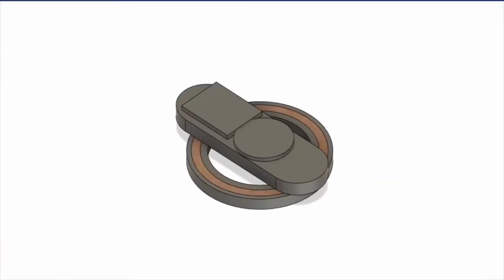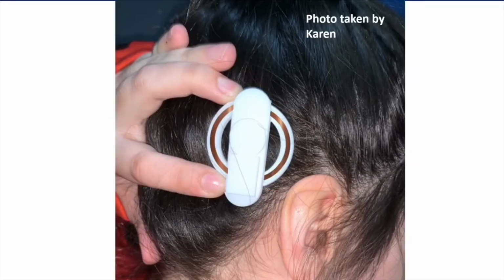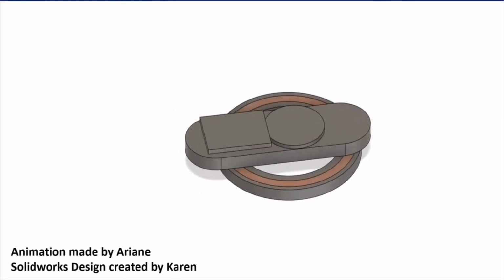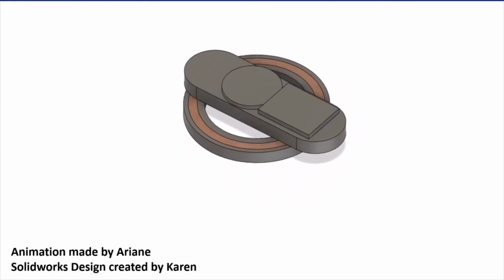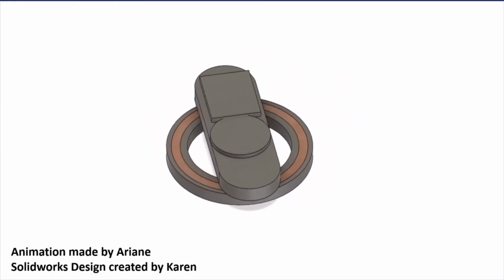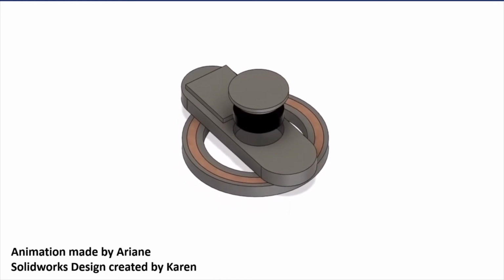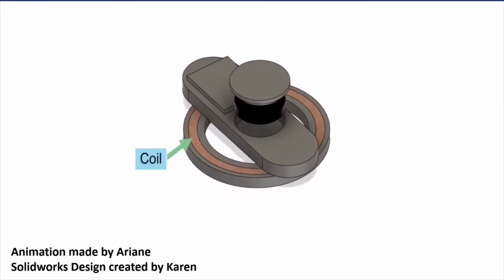The outer transmitter powering coil would ideally be worn behind the ear on the head. A compartment for the magnet on the external coil is shown here. There is an identical powering coil on the inside of the head that has a magnet as well. The two magnets are attracted to each other through the skin, and the outer powering coil will begin to power the device implanted inside.